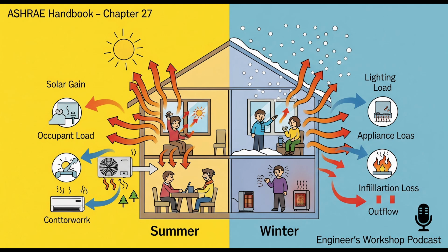Got it. And while the outside temperature is obviously the main driver, the sources really stress how important wind speed is for heating. Wind. Why wind? Because wind drastically increases infiltration, those air leaks we talked about. It forces more cold outside air into the building through all those tiny cracks and gaps. So a windy, maybe not that cold day could actually be worse for heating than a dead calm but much colder day. It absolutely could be. The worst case heating need might be a specific combination of temperature and wind, and it varies depending on how airtight the house is and the local climate.